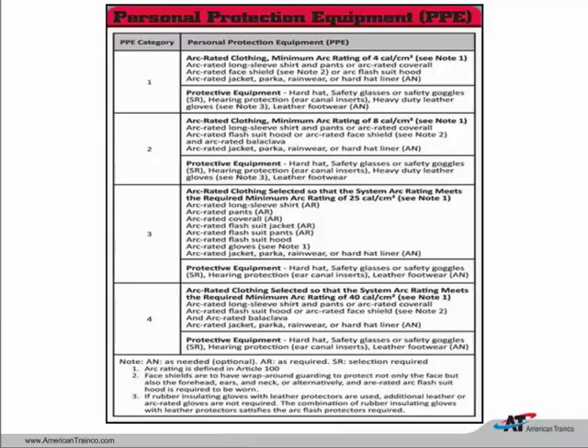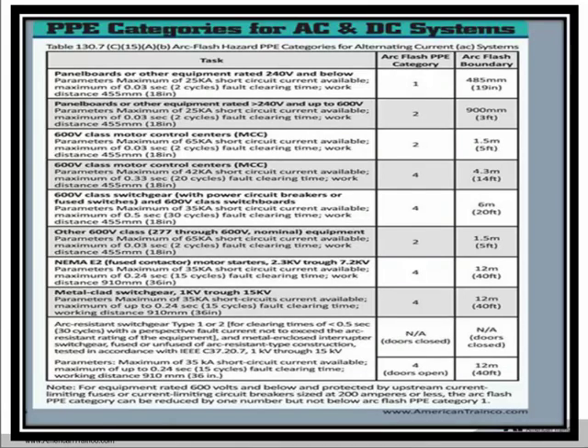So if we get above a level 2 PPE category, we're going to have to go with some arc rated gloves for 3 and 4. Now this system only goes up to 40 calories, as long as you can satisfy the parameters that we saw in the previous slide. I'll give you an example. We'll take an example of switchgear right here. If we satisfy this parameter, under 35,000 amps of available fault current and our clearing time is a half a second or less, then we would be in PPE Category 4 with an arc flash boundary of 20 feet.